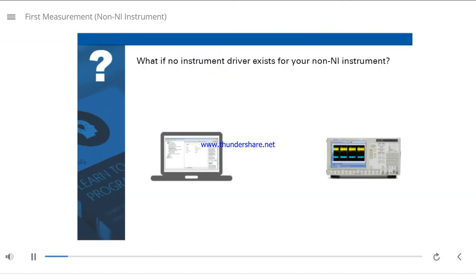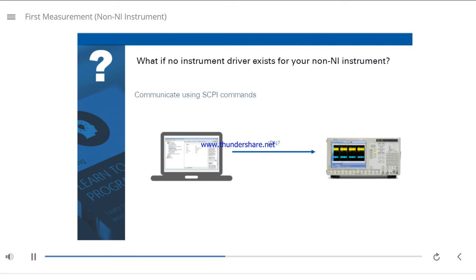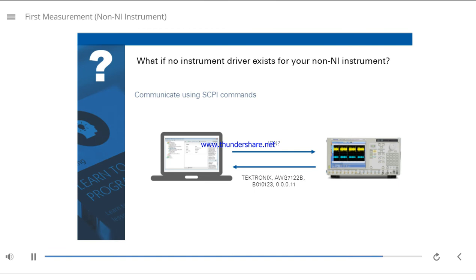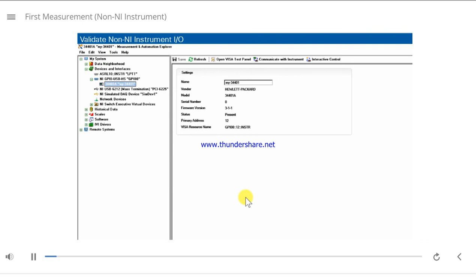If no instrument driver exists for your non-NI instrument, you will need to communicate with the instrument using SCPI commands. SCPI stands for Standard Commands for Programmable Instrumentation. In this example, the computer sends a *IDN? SCPI command to the instrument, which asks the instrument to identify itself. The instrument responds by returning a company name, model number, serial number, and firmware revision string. Refer to your instrument's manual to determine which SCPI commands work with your instrument.